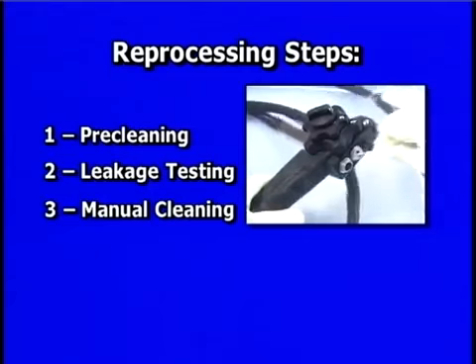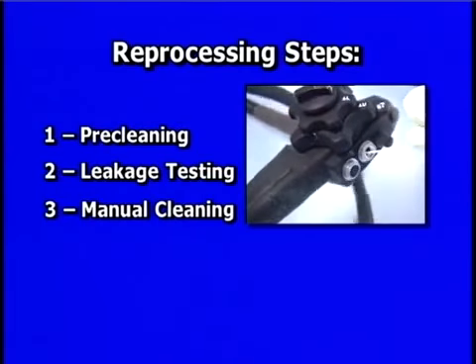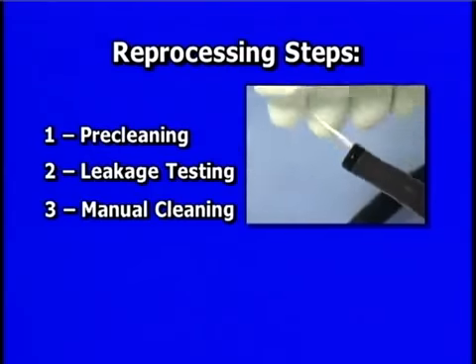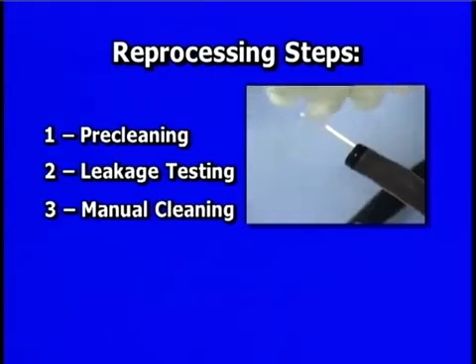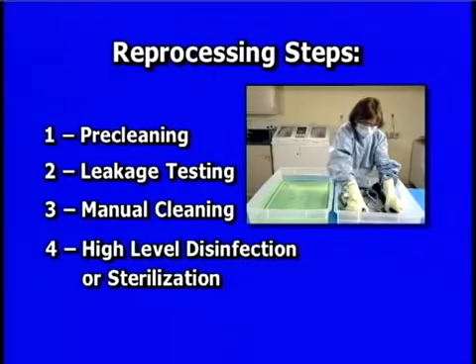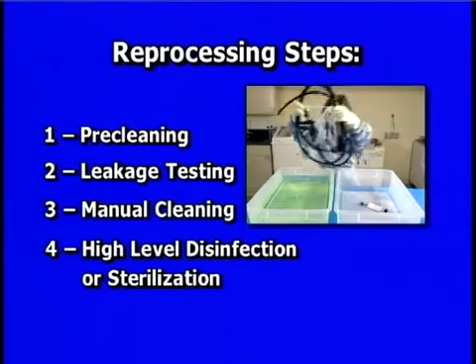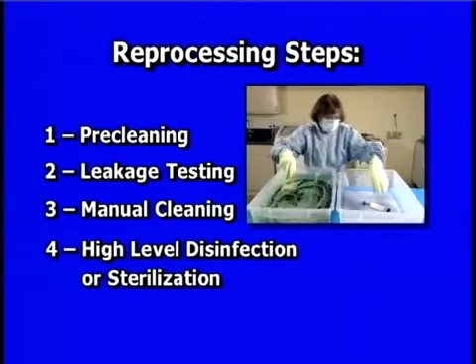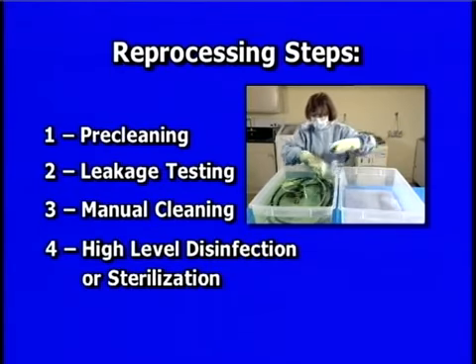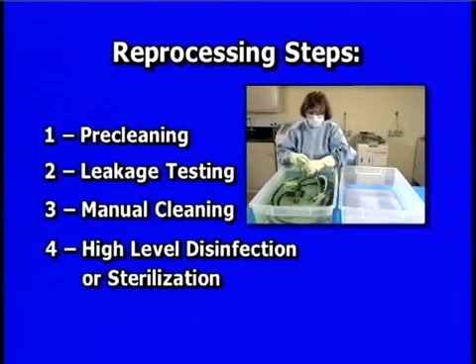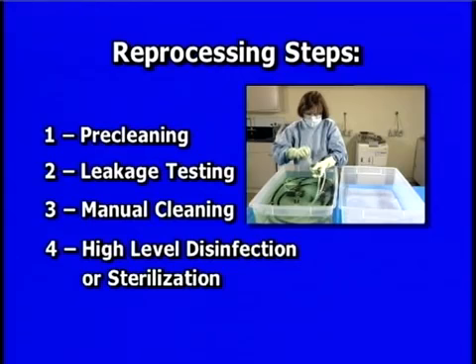The third step is manual cleaning. This involves thoroughly cleaning the exterior surface, all internal lumens of the endoscope, and all removable parts by wiping, flushing, brushing, and rinsing all surfaces. The final step in the process is high-level disinfection or sterilization. High-level disinfection is performed by immersing the endoscope in an FDA-cleared high-level disinfectant and ensuring that all surfaces are contacted for the specified time and at the temperature recommended by the disinfectant manufacturer. As an alternative to chemical disinfection, the endoscope may be sterilized using an approved method indicated in the reprocessing manual.